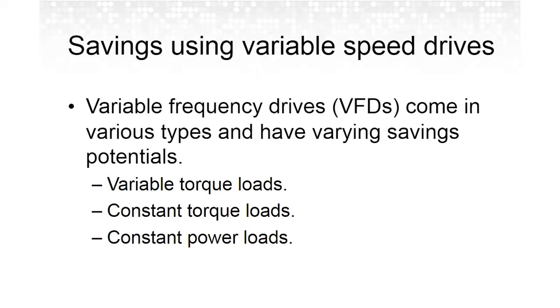So as an example, if you reduce the speed 50%, the full load torque is 25% of the full load. And if you reduce the speed 50%, the horsepower is now down at 12.5%. So that's a significant reduction in the horsepower required to run the load if you can reduce the speed 50%. Now, if you get a constant torque load, such as a hoist or compressor, the horsepower changes linearly with the speed. So with a constant torque situation, if you reduce the speed 50%, you reduce the horsepower 50%, not the 87.5% reduction that you get with a variable torque motor.